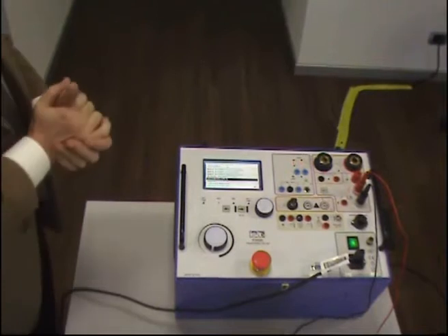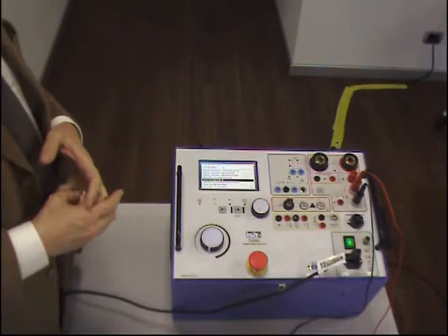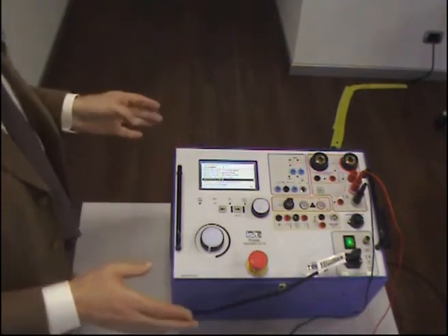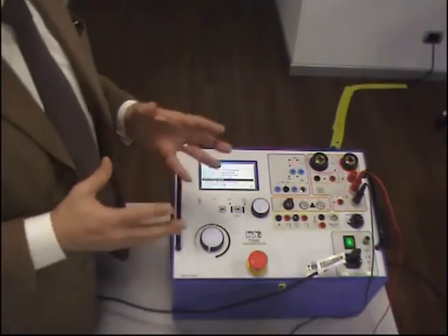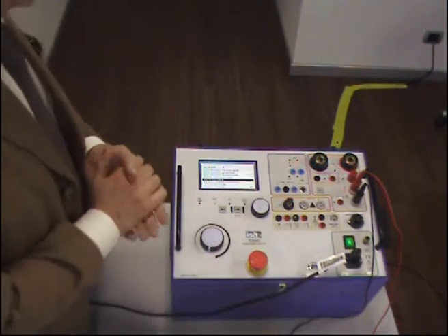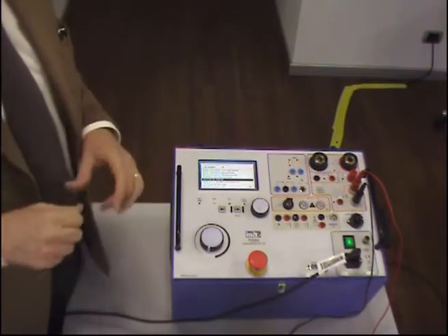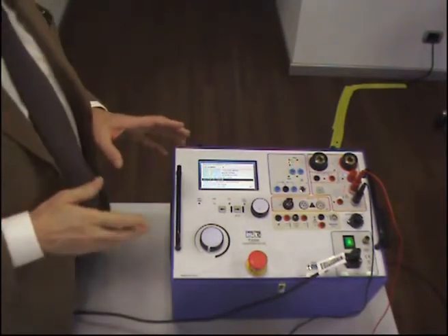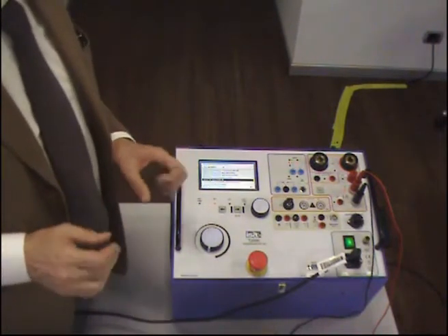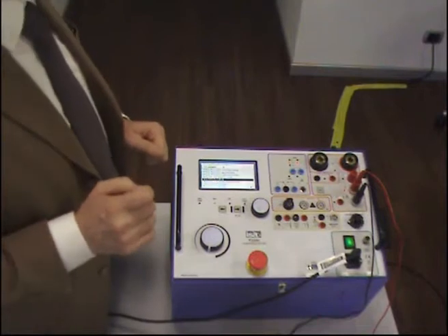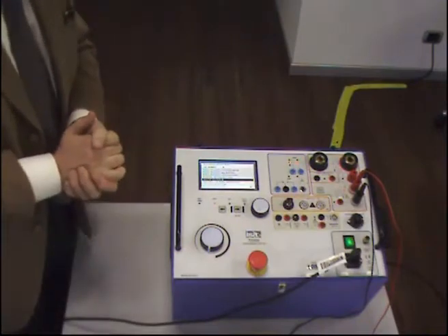The next and the most interesting test is the excitation curve test that allows us to verify the knee point of the current transformer. In this test, what we do is apply a voltage to the secondary side of the current transformer, and increasing it, we reach a moment when the current increases very much. Now, there is an IEC definition of the knee point. The knee point is the point when, increasing the voltage by 10%, the current increases by 50%.